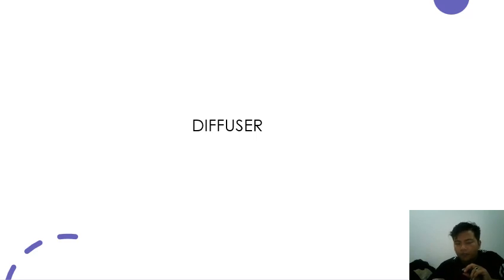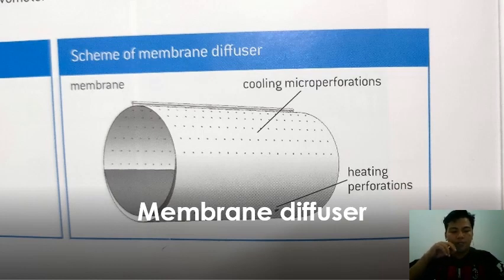The third classification is diffuser. Bmmh Malaysia provides 9 types of diffuser for building owners according to building application. The first one is the membrane diffuser. This is a combination of two types of diffuser into one. The beginning of the membrane is a lightweight, non-permeable material, sewn all along the duct length. The end of the membrane is attached to a pipe, which is controlled by servo motor or manually. In heating mode, the motor moves the membrane to cover the cooling diffuser located at the top of the duct. The supplied air exits the heating perforation on the bottom of the duct. In cooling mode, the motor moves the membrane to cover the heating perforation at the bottom of the duct, and the cool supply air leaves the perforation at the top of the duct. The membrane allows two totally different diffusion styles in one duct.